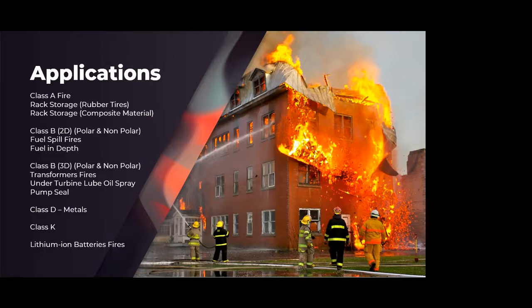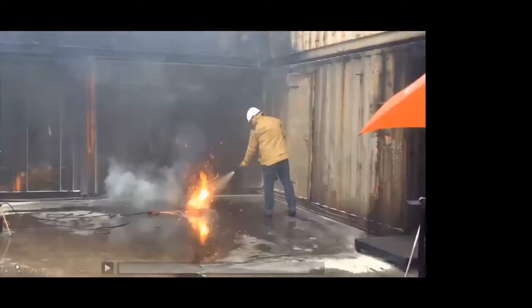We would be able to put detection equipment in, detect that vapor release, automatically send the signal to the control panel, have the operators isolate that valve, and shut that area down to shut off the flow of fuel while we dispense an encapsulator agent through the vapor cloud, removing the hazard, preventing the explosion, preventing the ensuing fireball, preventing damage and possibly injury and loss of life to people.